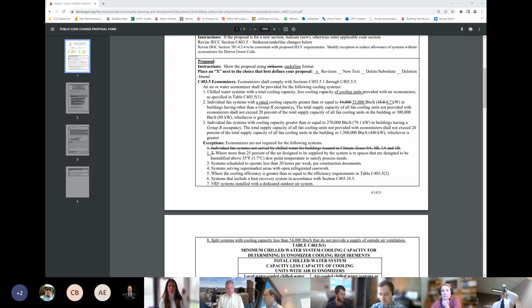And that's a real problem. It doesn't show up in the color brochures. It only shows up in the installation instructions of these units. And when you talk to manufacturers, they essentially say you can't install a VRF system that effectively swaps heat from the interior to the perimeter. And then there's a whole lot of classifications of buildings that are thin or don't have a lot of interior heat to go around during the zone. So this whole question about VRF systems not needing an economizer has just been totally misread, misspoken by the manufacturers. It doesn't work that way.